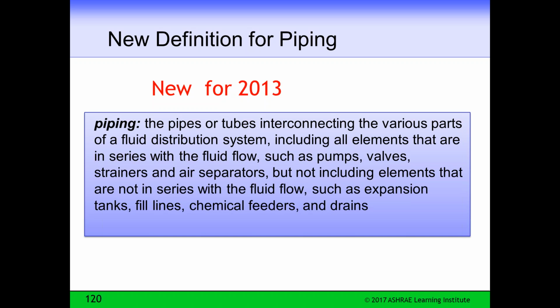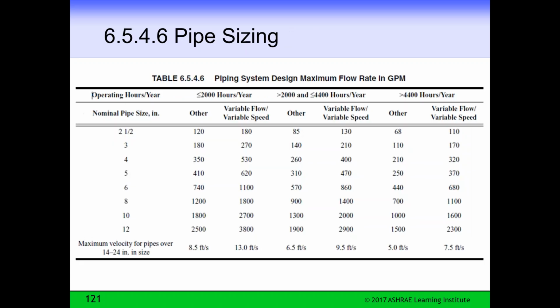So now you know what piping is, and the reason we did that was because we require you to insulate all piping. So you have to insulate the heads of the pumps, valve strainers, and separators, but not the expansion tank fill lines or chemical feeders and drains. So now we've helped define what we mean by piping when we talk about insulation. We also have requirements for pipe sizing.